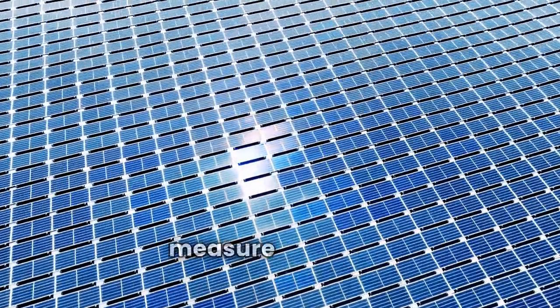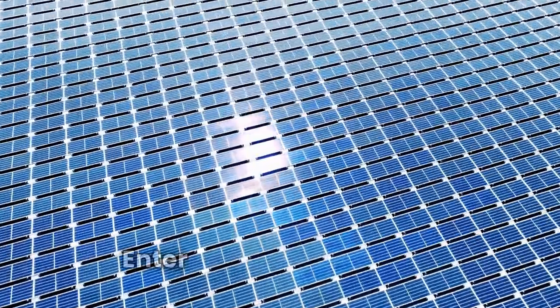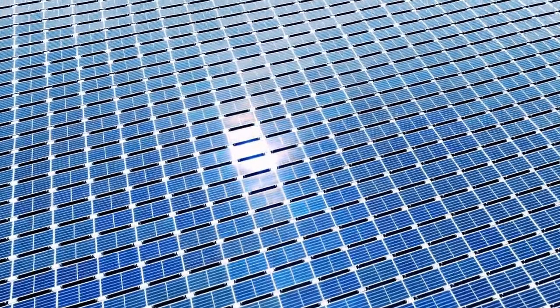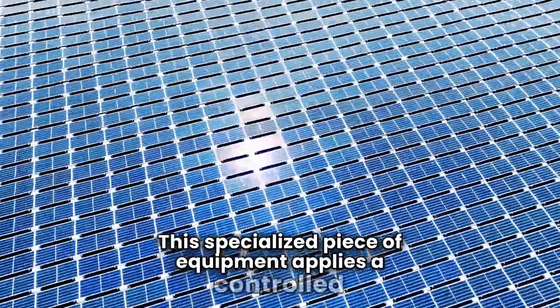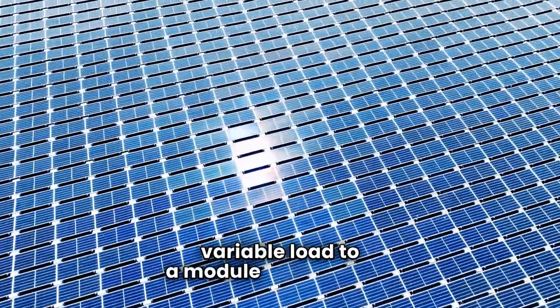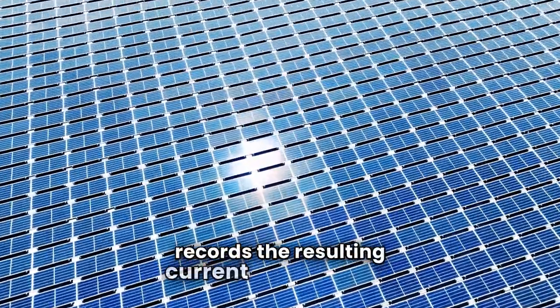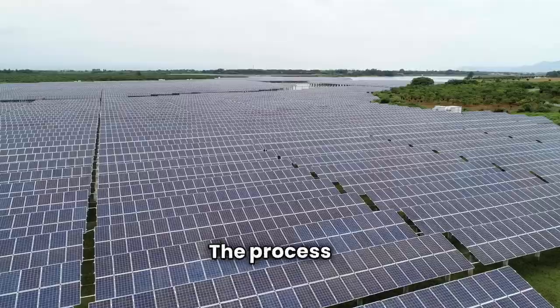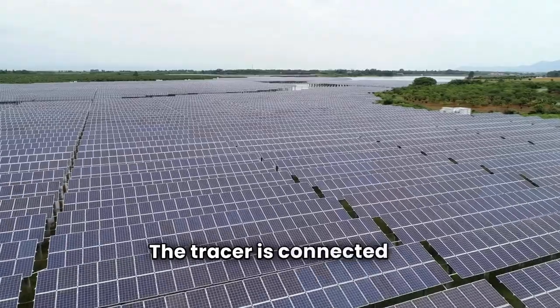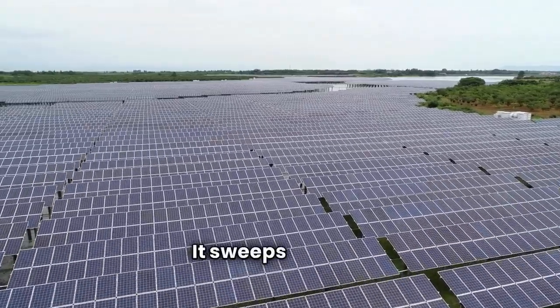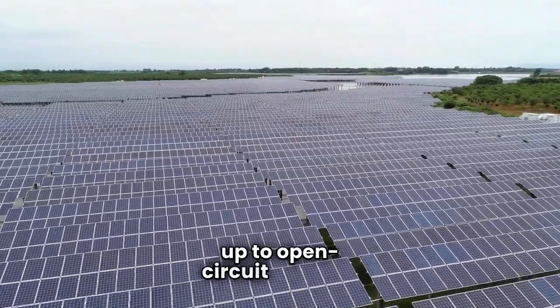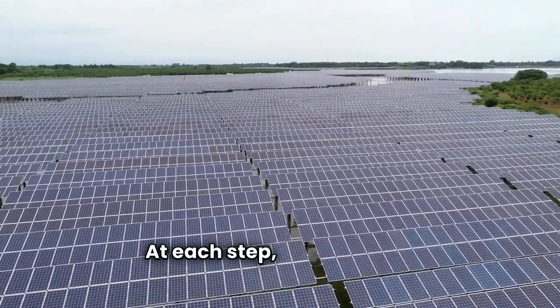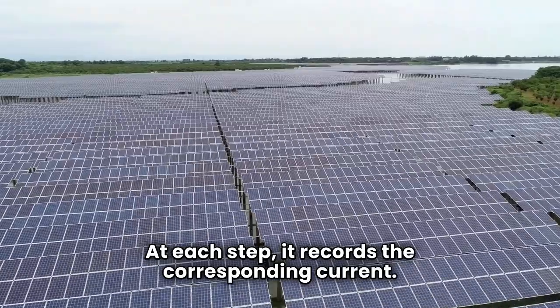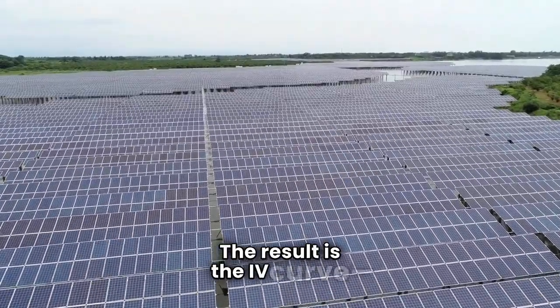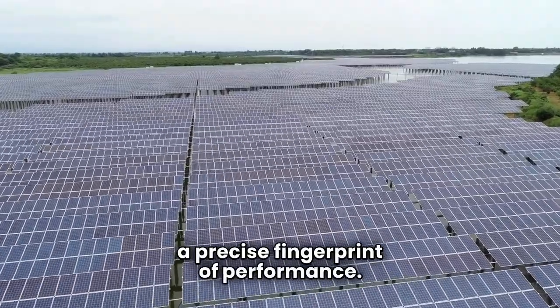So how do we actually measure IV curves in the field? Enter the IV curve tracer. This specialized piece of equipment applies a controlled variable load to a module or string and records the resulting current and voltage. The process is straightforward. The tracer is connected to the module or string. It sweeps voltage from zero up to open circuit voltage. At each step, it records the corresponding current. The result is the IV curve, a precise fingerprint of performance.